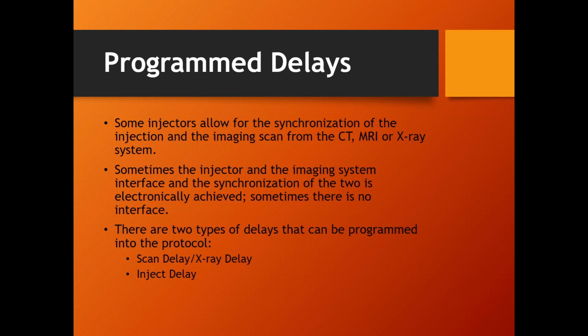Now sometimes they want both systems to start at the same time. Hit both buttons and boom, they're both shooting at the same time. But that's not always the case. Sometimes I want one to start and then the other one to start so many seconds later. So the first kind of delay that we're going to talk about is inject delay, and it's just exactly as it sounds. The imaging system is going to start, and then so many seconds later, the injector starts. That's called inject delay.